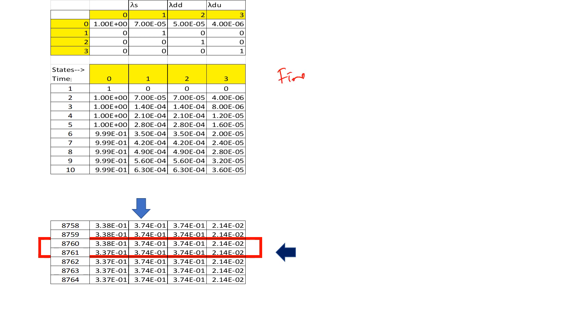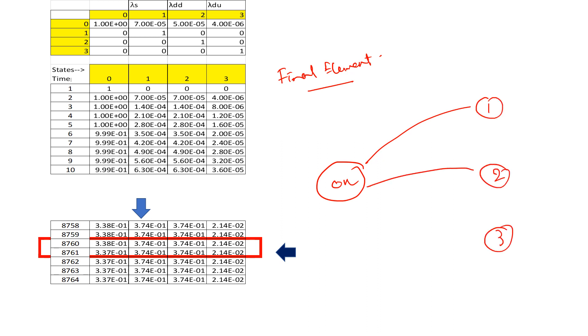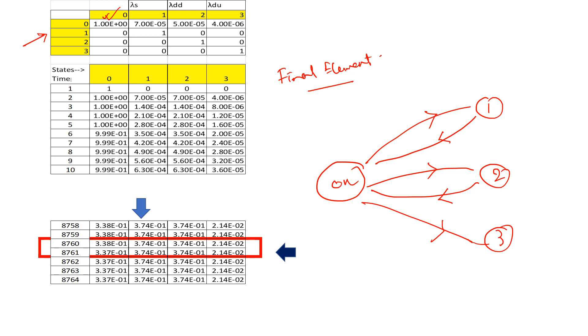Similarly we can get the PFD average value for the final element using the same approach. One aspect missing here is repairability — normally repair is possible from the fail safe state and the fail dangerous detected state. For simplicity we have not included repair here; including it would add transitions back from states 1 and 2 to state 0, increasing the probability of the OK state. The current calculation is therefore more conservative.